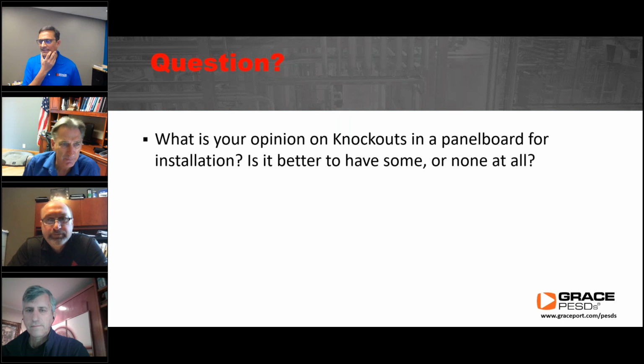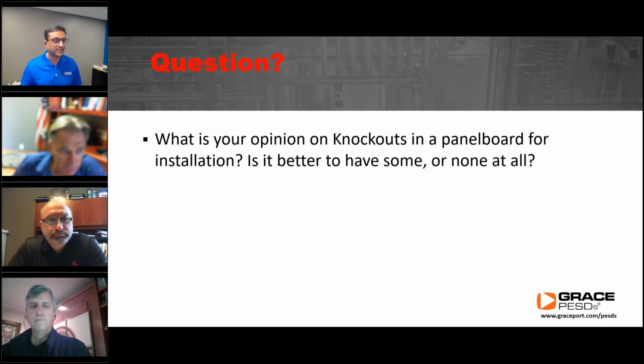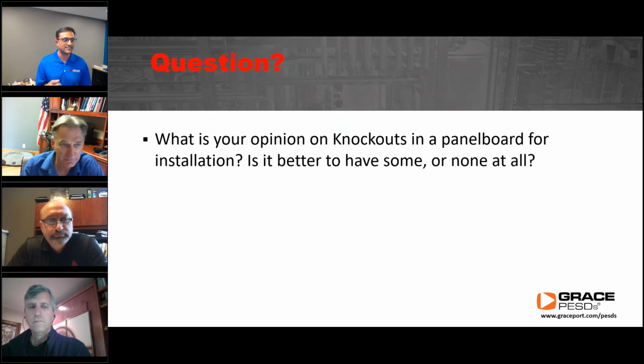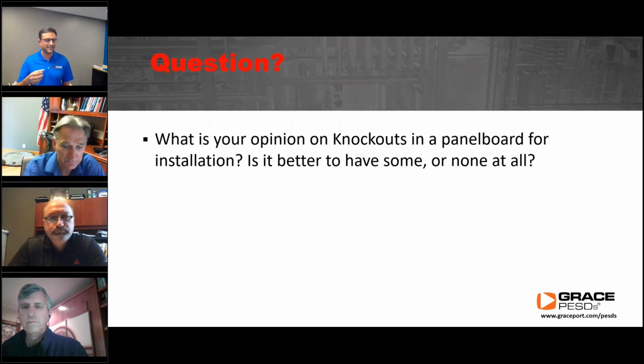Thanks, Charlie. My only comment is, if you have a knockout and you're using it, punch it. Or if you've punched one and it's unused, put a plug or something so you protect it from external rodents and such entering the panel. I've seen situations where the electrician is doing this work and he's punching that knockout but not using that conduit, just leaving it open. I think that's a bigger mistake, I would think so.